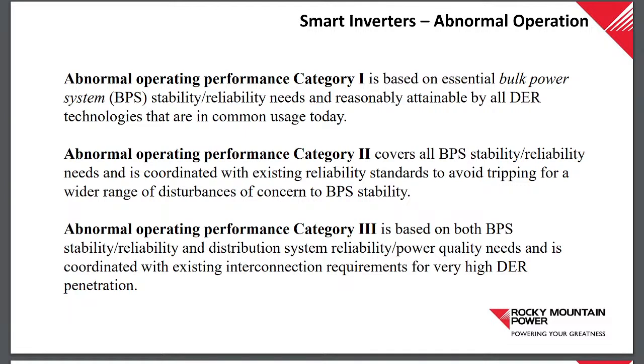It's coordinated for interconnection requirements with very high DER penetration, right, so that's where we're seeing a lot of generation compared to the load on the circuit. So you're going to hear a lot about minimum daytime loading, DER penetration, high penetration, hosting capacity. That's where this Category III comes in, and it allows for the ranges to accommodate examples of high penetration areas, where the generation is creeping up to meeting the load, so we don't have excess and reverse flow at the circuit breaker. That's what that's all about.